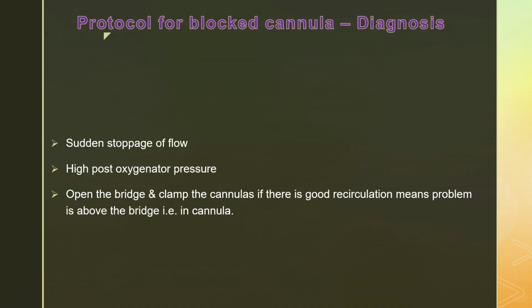See, if your delta pressure is increased, then it is going to be oxygenator failure. If both P2 and P3 are increased, it means there is something wrong after the oxygenator. Okay, so it can be a blocked cannula or a blockage after the oxygenator. Okay, that is one way. The second way of confirming it: if there is a bridge in the circuit, you can clamp the cannula, open the bridge and start the circuit. If the circuit starts moving, it means there is nothing wrong in the circuit. The blockage is in the cannula. Okay.